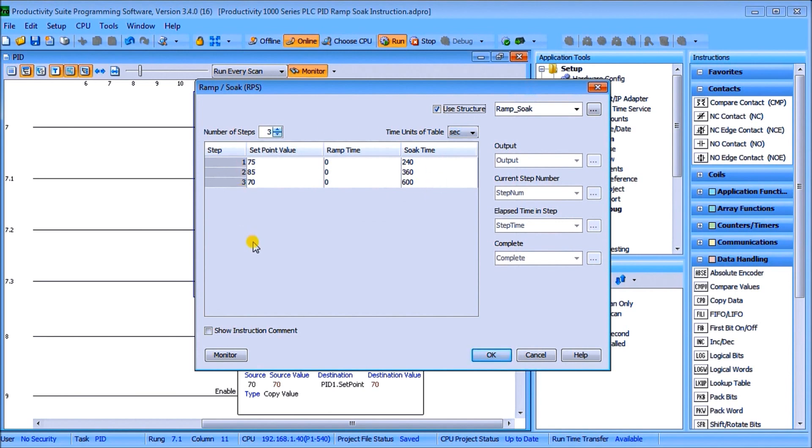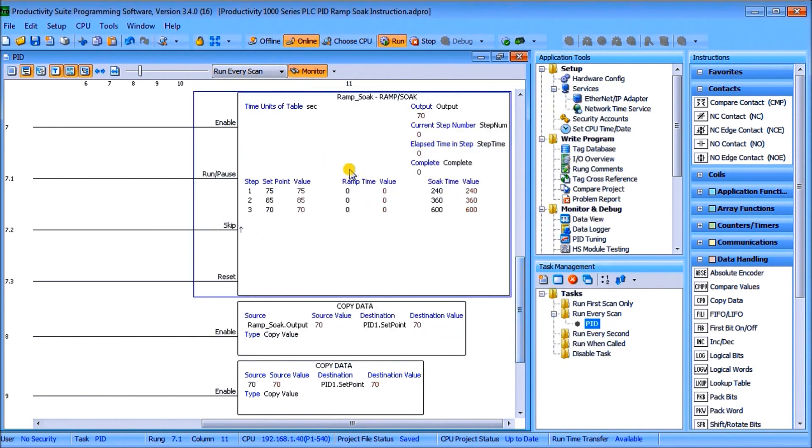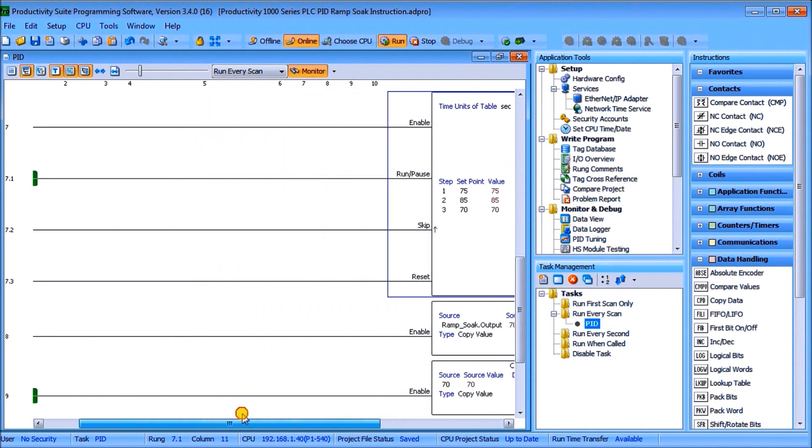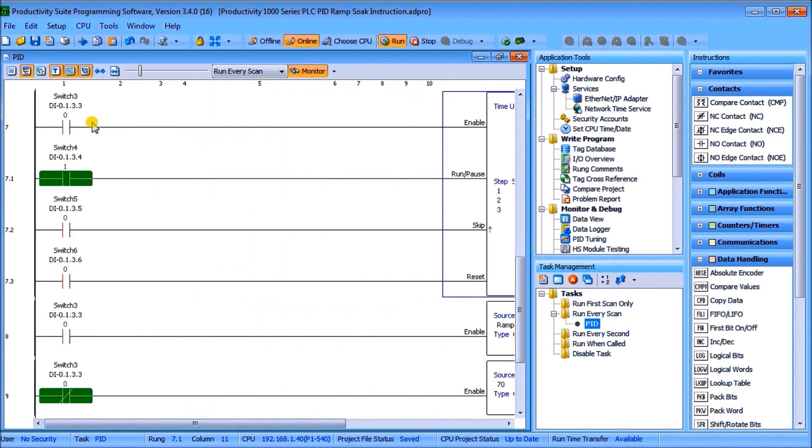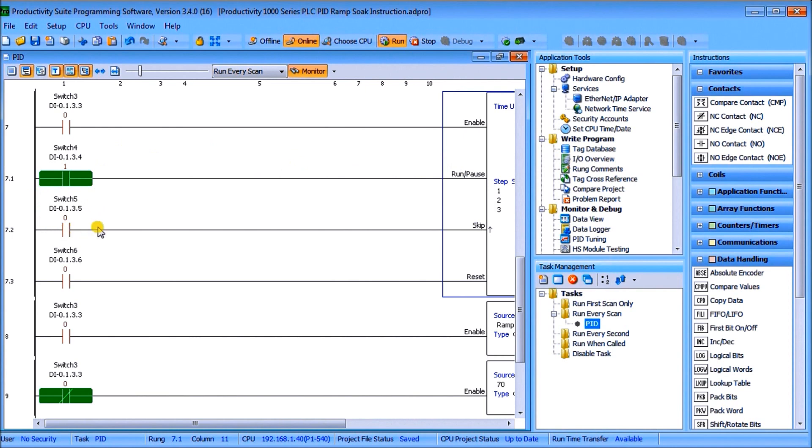So that's actually our instruction and we can have our number of steps here, we can have up to 16 of these steps on our ramp soak and we've used a structure here we call it ramp soak. And then you'll see we have switch number three to enable it, switch number four keeps it in run or pause, and then we have switch number five which is our skip so we'll skip that step and then switch number six will reset that unit or that ramp soak.